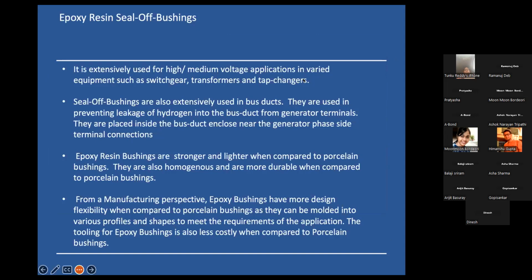So now coming to seal-off bushings, which is another insulator product which we manufacture. Seal-off bushings have a wide variety of applications. They're used in transformers, tap changers, and also in various switchgear. Specifically when it comes to switchgear, they're used a lot in bus ducts.